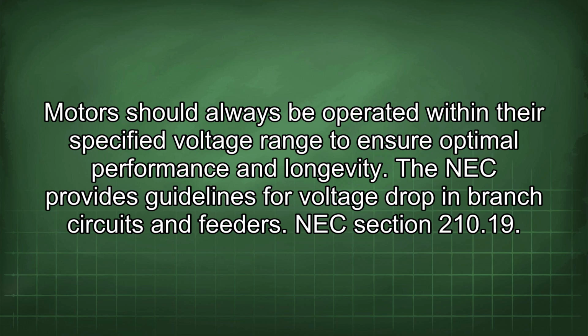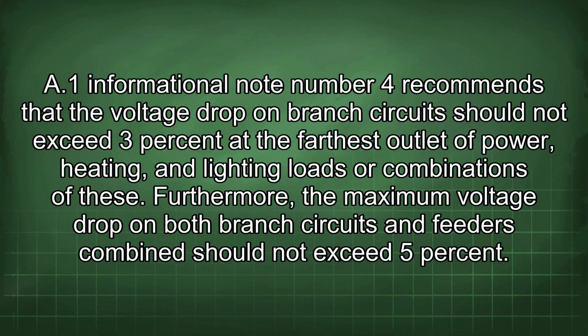The NEC provides guidelines for voltage drop in branch circuits and feeders. NEC Section 210.19(A), informational note number 4, recommends that the voltage drop on branch circuits should not exceed 3% at the farthest outlet of power, heating, and lighting loads or combinations of these. Furthermore, the maximum voltage drop on both branch circuits and feeders combined should not exceed 5%.